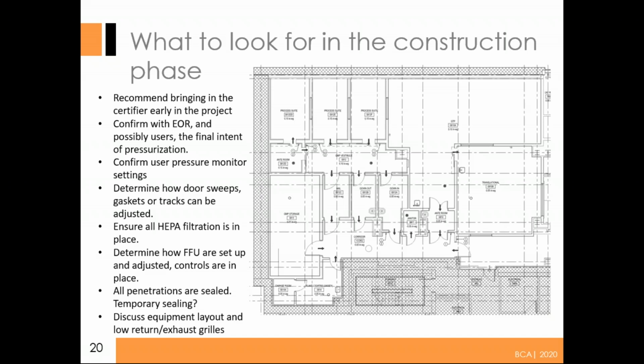Confirm with the engineer of record what the final intent of the pressurizations is. Even though you might get a drawing from the design team, it could be wrong, or the users might have a different interpretation of what they want to do with some of these rooms, and the pressures might need to change. Confirm user pressure monitor settings. Some of these clients might be getting a pressure monitor for the first time, or they might be getting some of these newer, more complex ones for the first time. So try to get the settings that need to be put in place ahead of time.